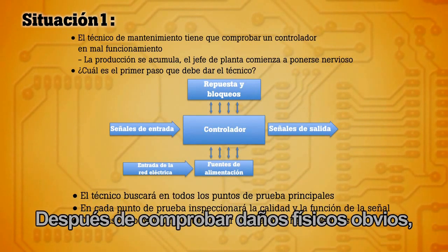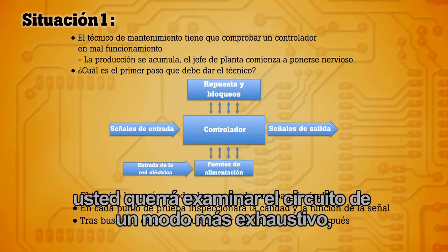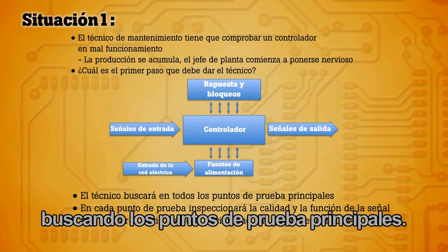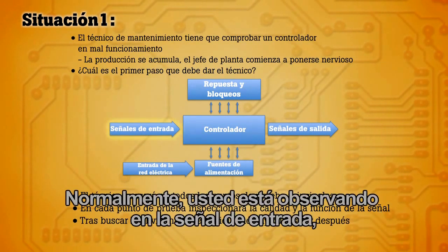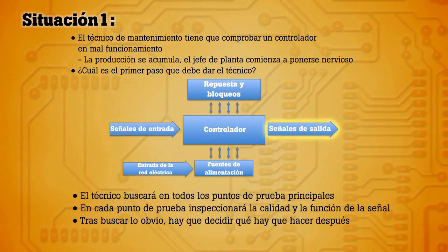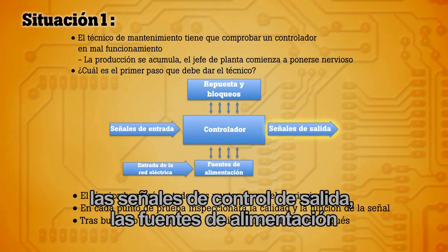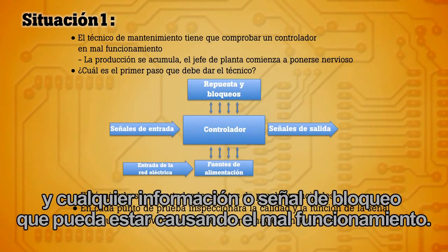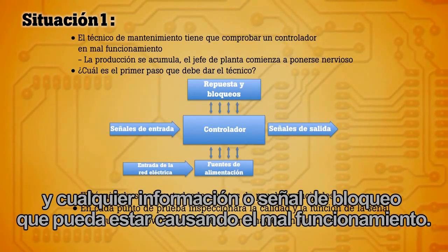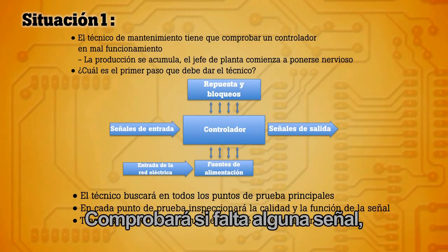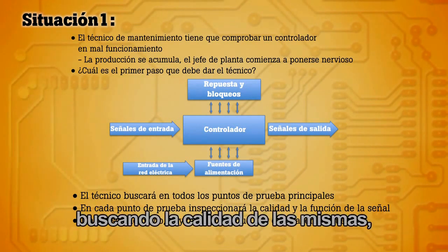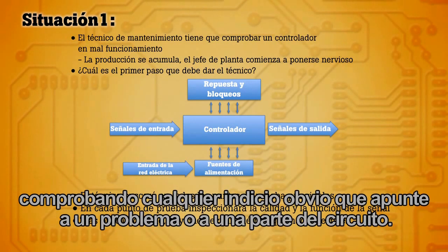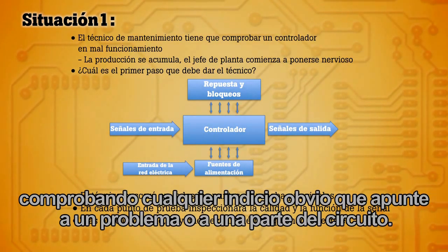After checking for any obvious physical damage, you'll want to take a look at the circuit at a high level, looking at key test points. Typically you're looking at the input signal, the output control signals, the power supplies, and any feedback or interlock signals that might be causing the malfunction. You'll be checking for any missing signals and looking at the quality of the signals, checking for anything obvious that could point you to a problem on any part of the circuit.